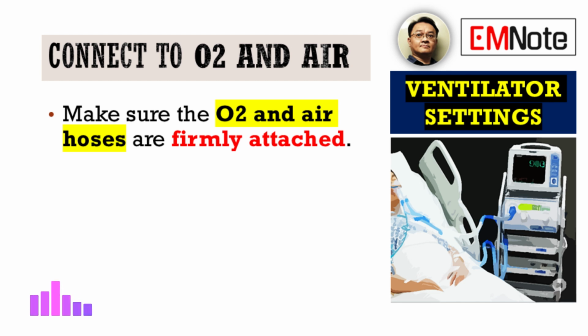After assembling the entire breathing circuit, you have to ensure the high-pressure hoses for oxygen and medical air are firmly attached to the ventilator's gas inlets. These are the main lifelines, connecting the hospital's gas supply right to the machine. Loose connections at this point can lead to immediate ventilation failure, insufficient gas delivery to the patient.